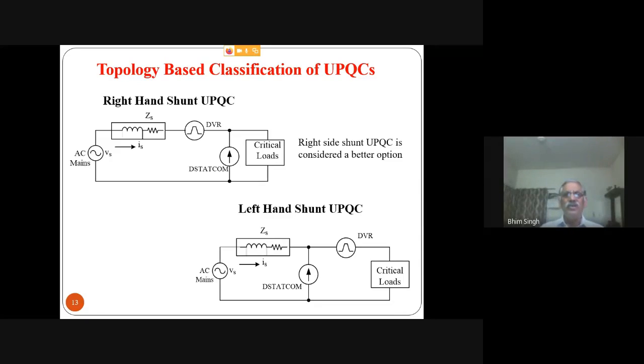Because in a transmission system you don't have harmonics; you only require reactive power. But once you come to a distribution system, you have harmonics, and you also have unbalance, load unbalance and voltage unbalance. In a transmission system, you don't have unbalanced voltage or unbalanced current, and you don't have harmonics. The only requirement in a transmission system was reactive power. And moreover, in a transmission system, this side was not the load; it is a transmission line. The series compensator is put in series with the transmission line, and the shunt is put at the substation. So this topology was preferred in the case of your FACTS devices. But when we talk about the UPQC in the distribution system, we prefer this topology.